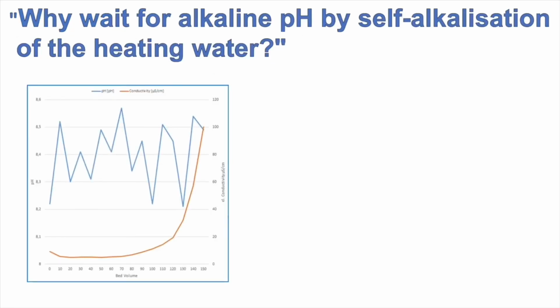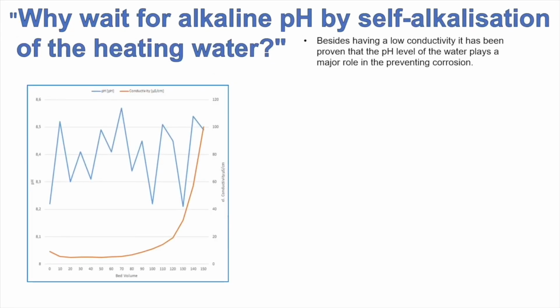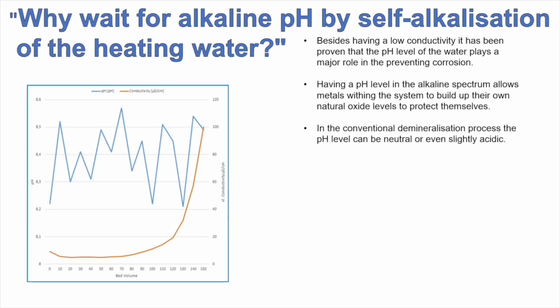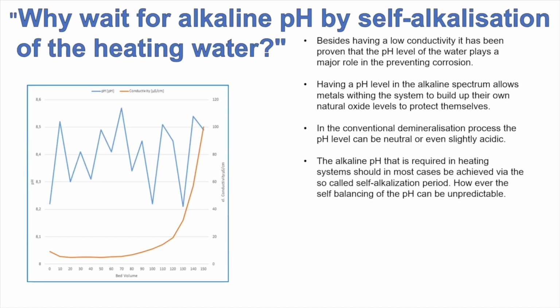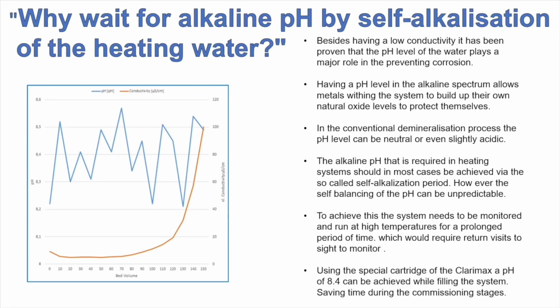So on this in the video, self-alkalization usually takes, we allow up to a whole heating season for it to happen. Using the Clarimax, we can actually get this to happen instantly, and we've demonstrated it in the video. Using the cartridge-based system, we're going to get a pH of about 8.2, 8.5 straight out of the cartridge, so ideal for our heating systems. We don't have to wait, we don't have to go back and retest, we're there already.